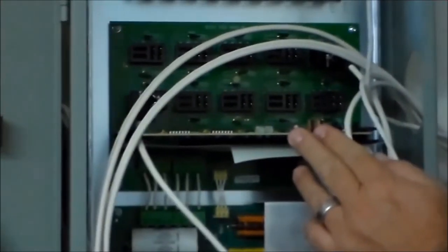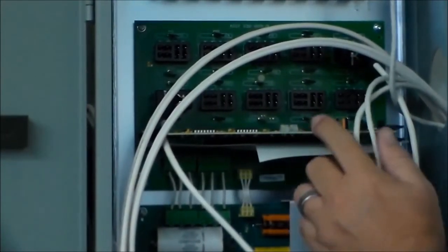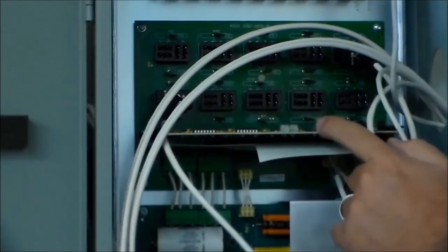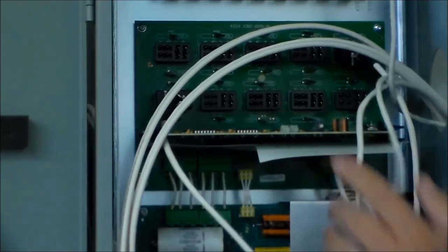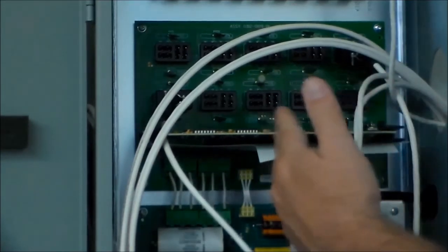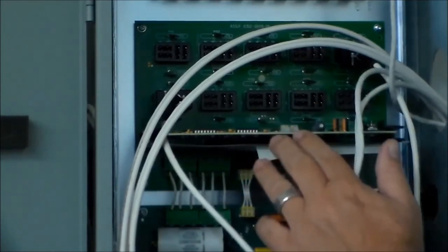The communication board has two LEDs and a push button. Push the button to check the status of the comm board. Two green lights indicate the system is working properly. If one or the other lights does not turn on, there is a problem.